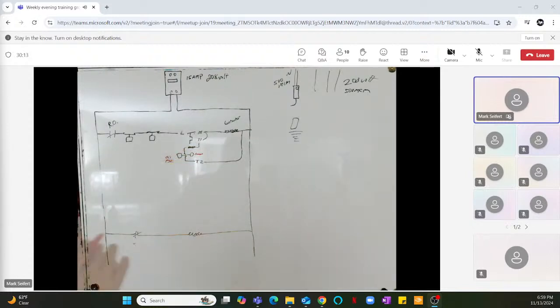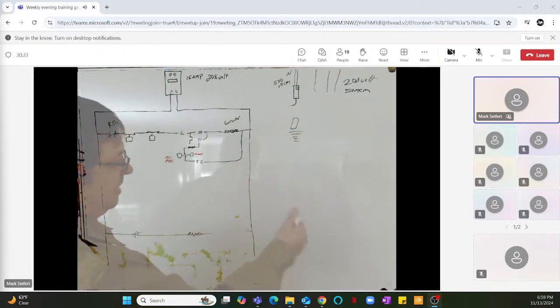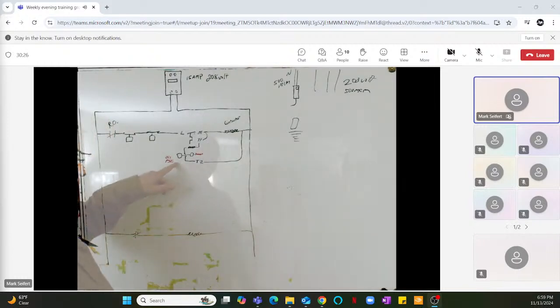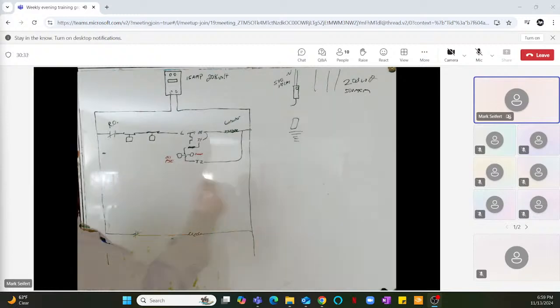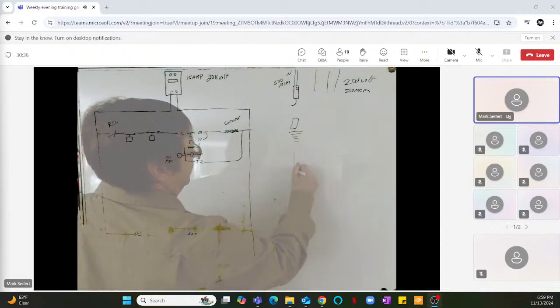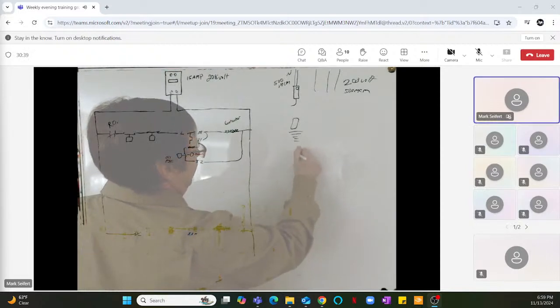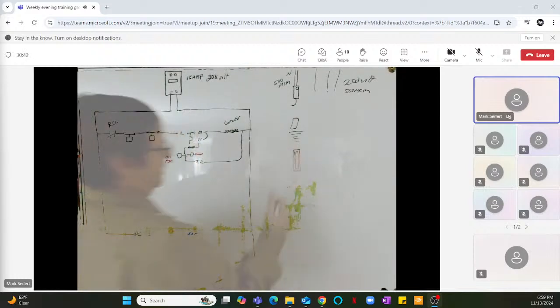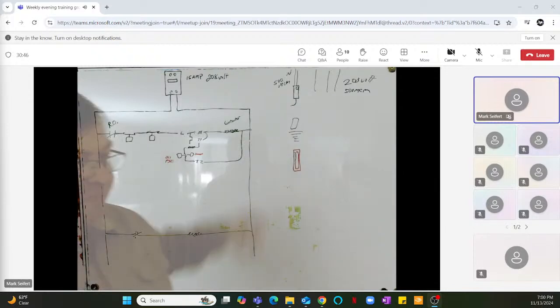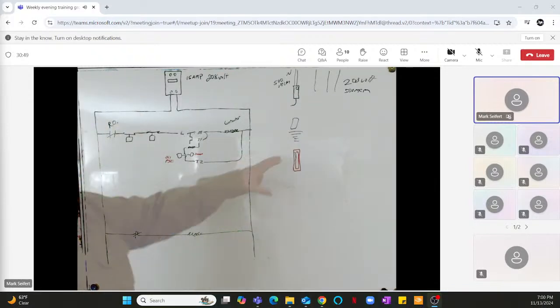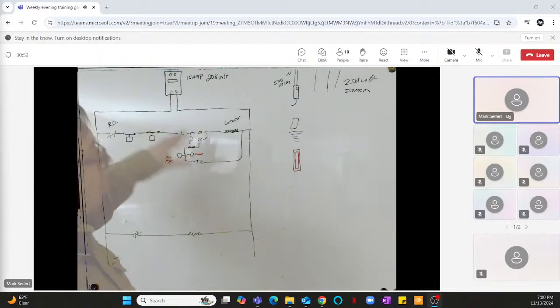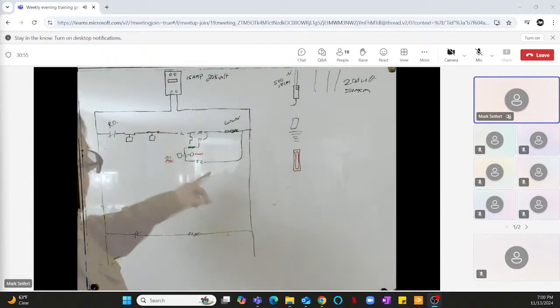Any questions on that? You follow me? Just forget about what I said about the little resistor. The little resistor, you feel your thumb on there, you can pull the cover off, and if that thing's hot, if it's getting warm, then your oil pressure is not high enough. You can tell by your thumb on that little, it looks like a rectangle thing that's got a weird shape in the middle. It's a white resistor right on the outside of it. And that just keeps the resistance doubled up so that you could use 208 volt or 120. You notice that they've got a 120 or a 240, right? You could use either.